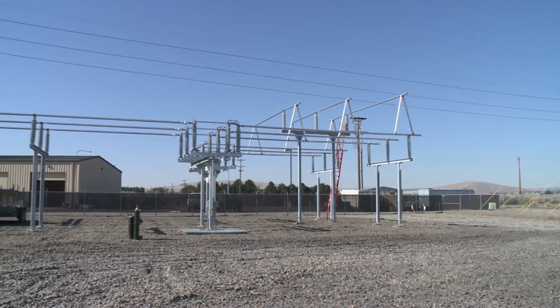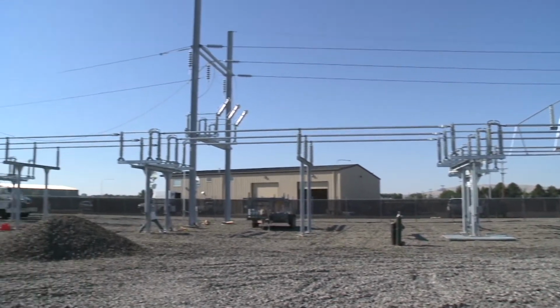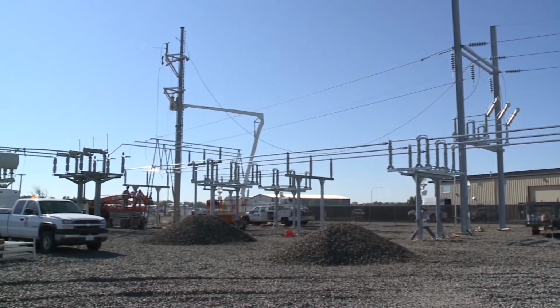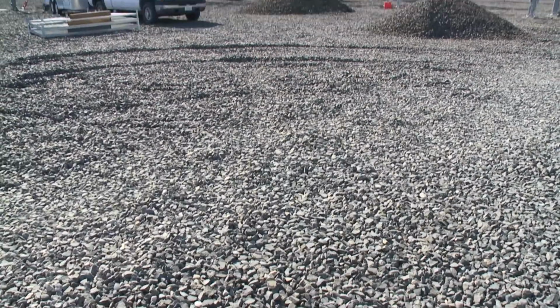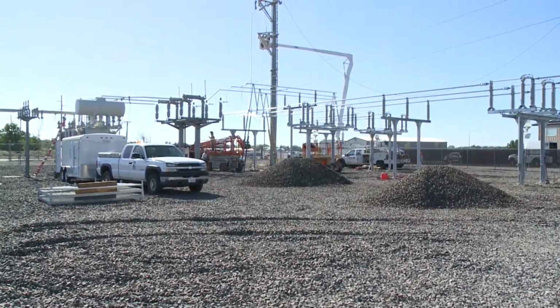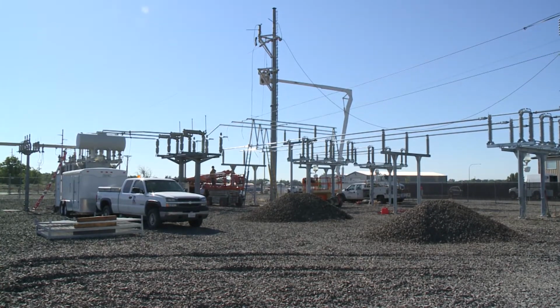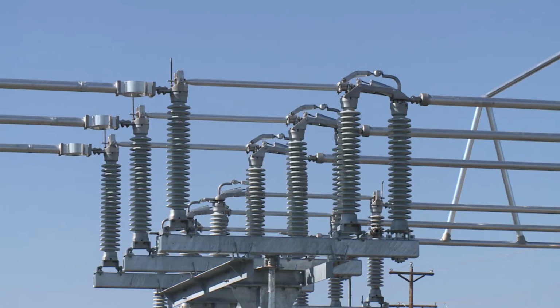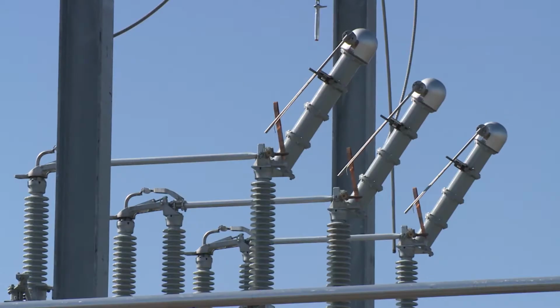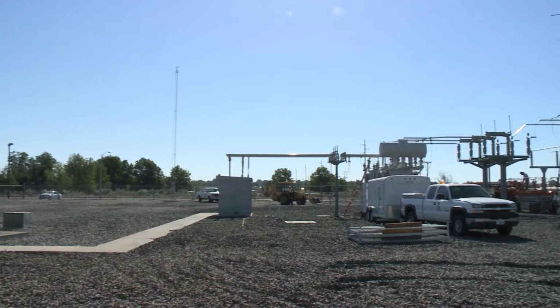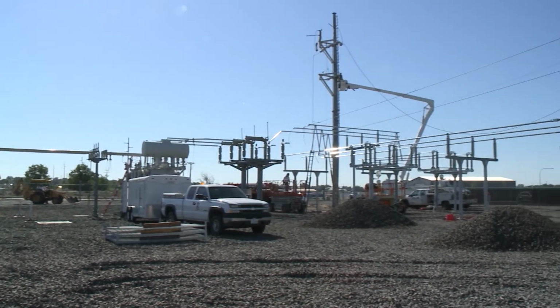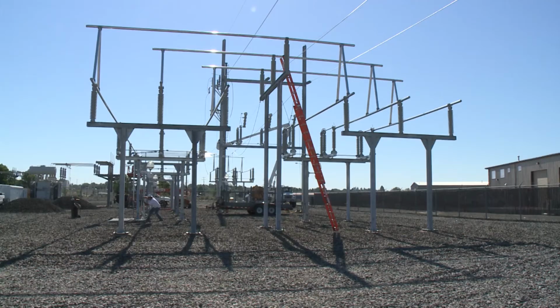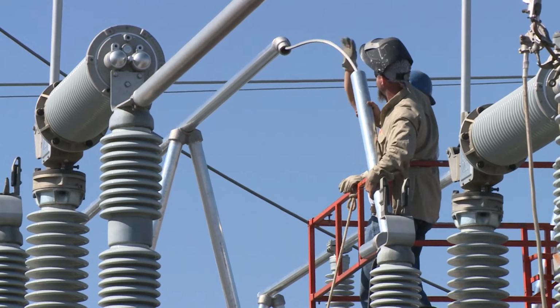To accomplish the eventual expansion of the substation, we needed to redesign it and add additional bays for future growth. As we add load in this region, we'll be able to, with minimal impact to other customers, de-energize a portion of the substation and install additional transformers and metal-clad switchgear.